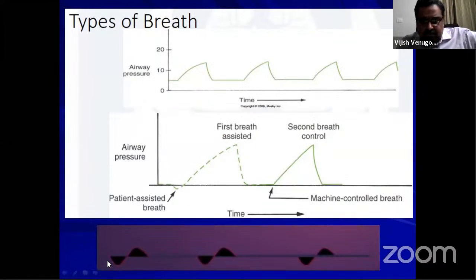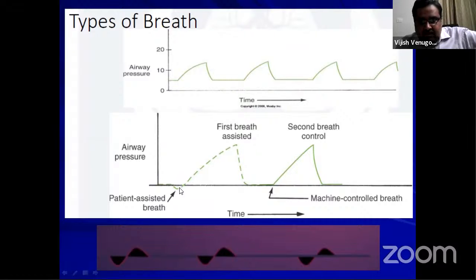I can show you a picture here. If you look at the bottom part, you can see a sinusoidal wave. So this is spontaneous ventilation, right? And if you look at the pressure tracing, I think you can see my arrow. You can see here that in the patient assisted breath, there is a dip in the pressures. So this is an assisted breath. Whereas in the second one, the bold line, there is no dip in pressure. So this second breath is a machine controlled breath.